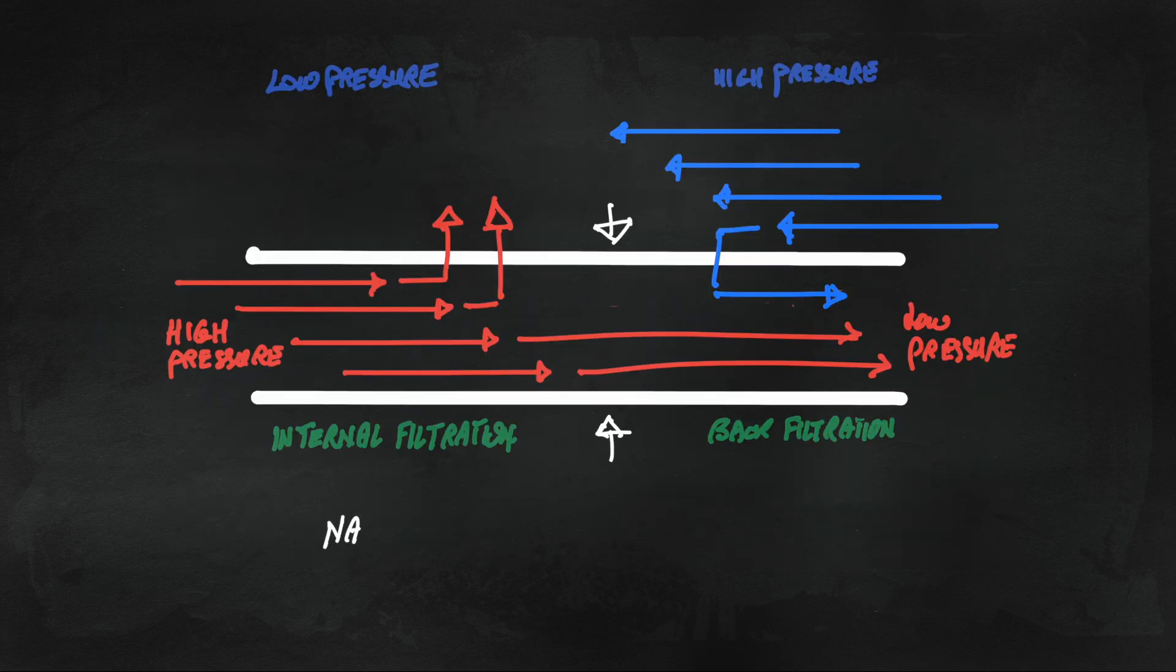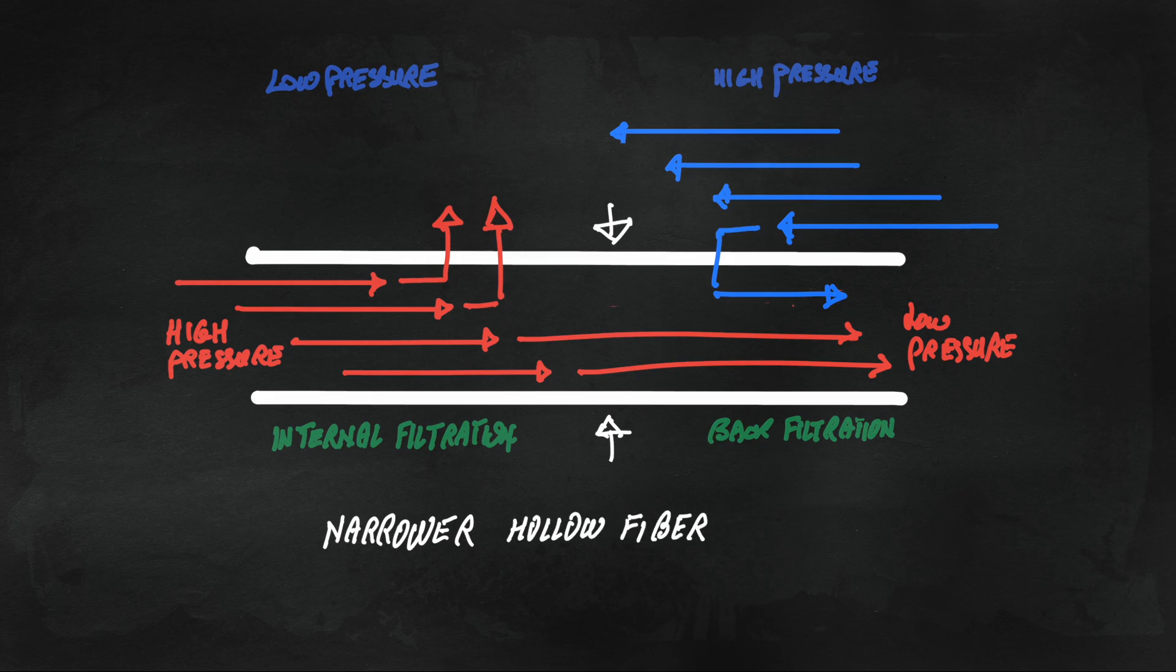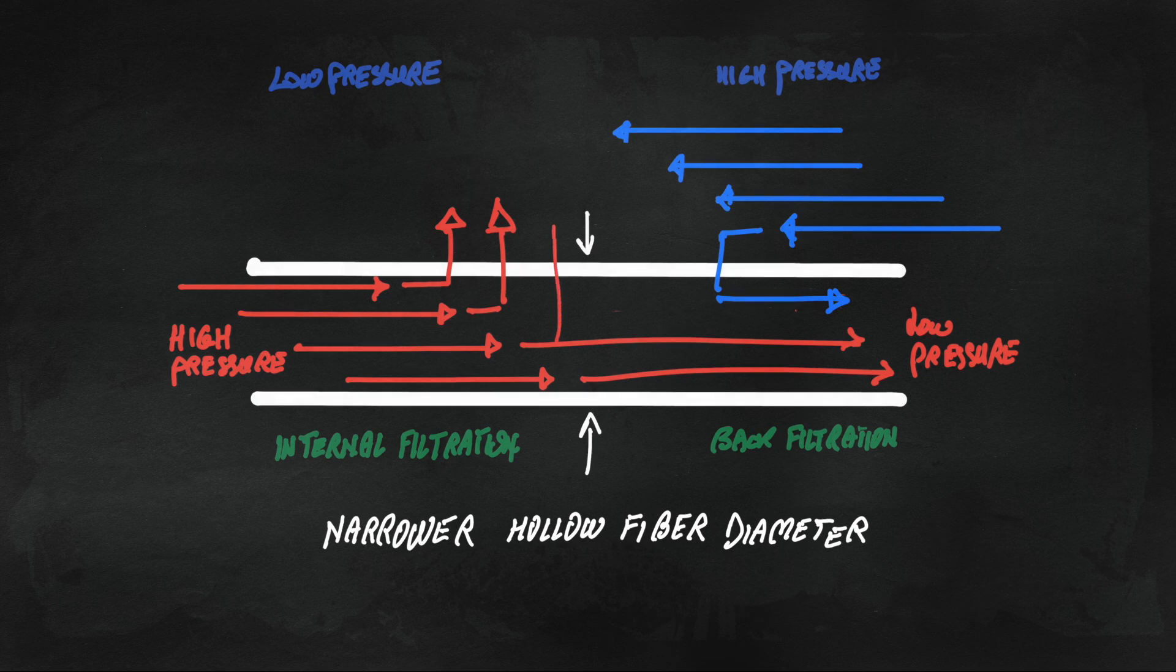The internal filtration back filtration can be enhanced by reducing the hollow fiber diameter where you have higher pressure buildup for the same blood flow rate.